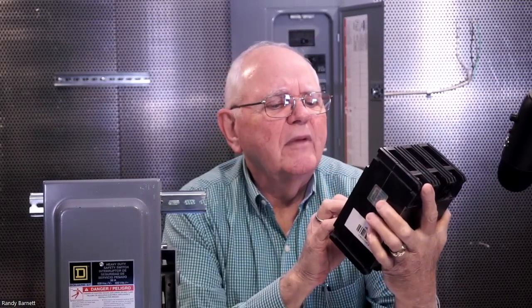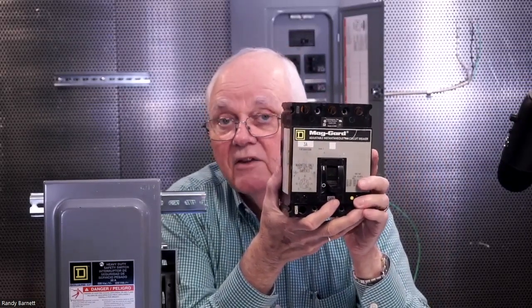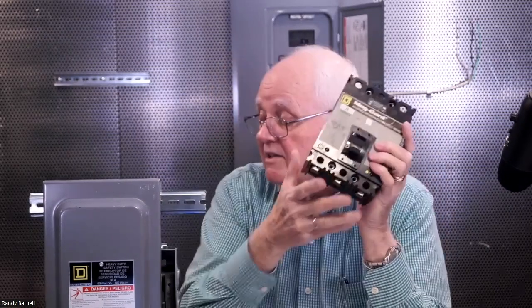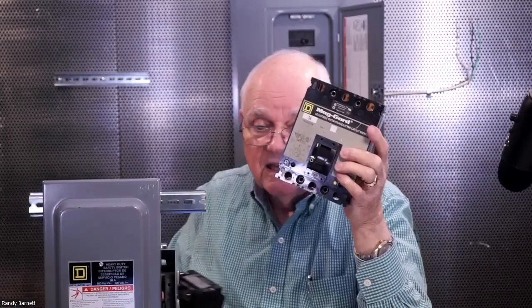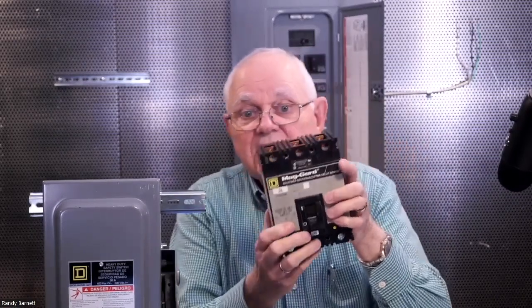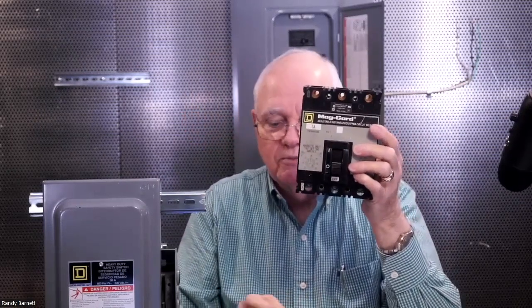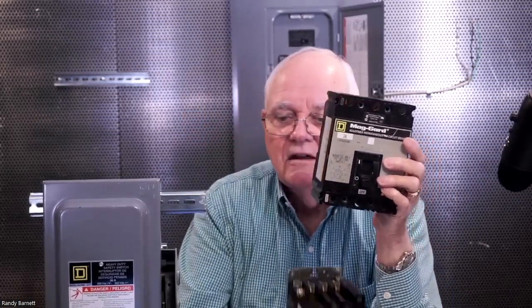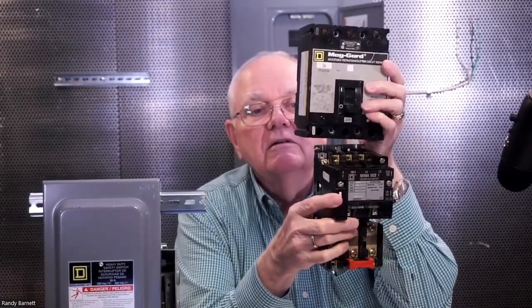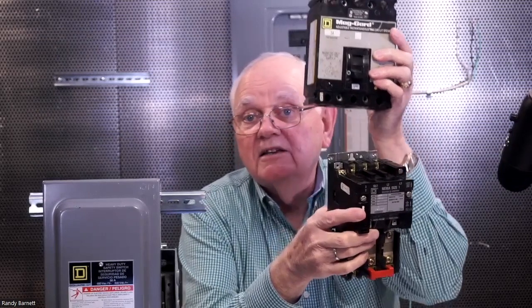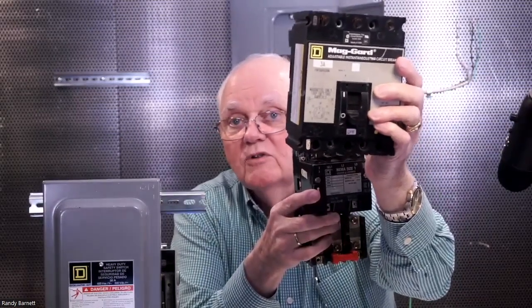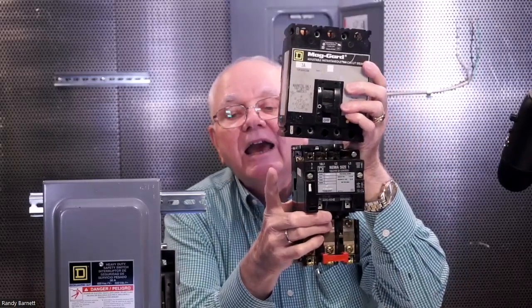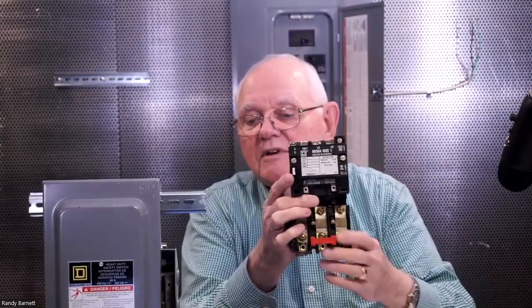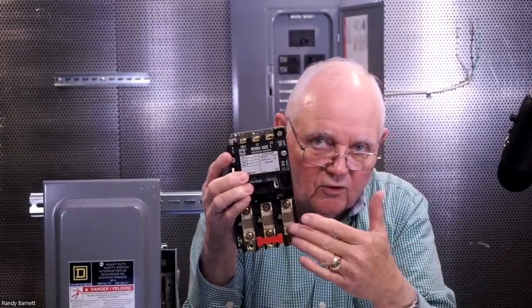Yeah, but I can adjust it from 8 times 3 amps to 28 times 3 for my instantaneous trip settings. This motor circuit protector is often used inside a motor control center, which is where this one actually came from. So if I take an entire unit and get it listed, I have my motor circuit protector, and then I feed from there into my motor controller. I've got a pretty good setup now because I've got ground fault and short circuit protection with my motor circuit protector, instantaneous circuit breaker. I have overload protection right down here at the bottom with the overload portion of my controller, the overload relay, in this case some bimetallic thermal devices.